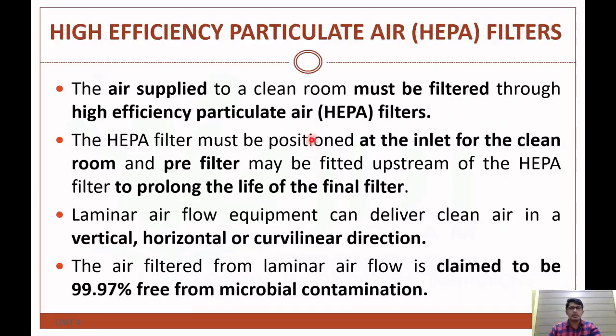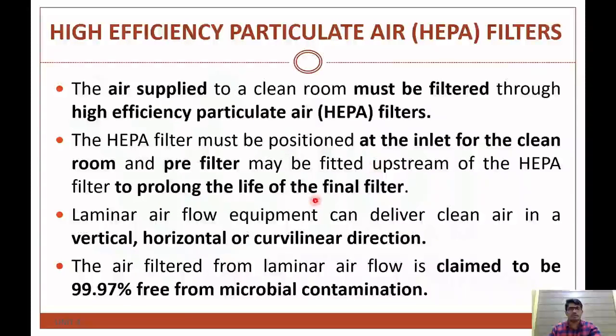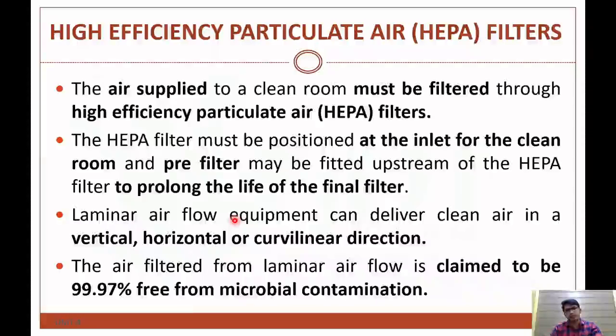The air supplied to the clean room must be filtered through a HEPA filter — that is, the High Efficiency Particulate Air filter. This filter must be positioned at the inlet for the clean room, and a pre-filter may be fitted upstream of the HEPA filter to prolong the life of the final filter. The laminar air flow equipment can deliver clean air in a vertical, horizontal, or curvilinear direction. The air filtered from the laminar air flow unit is claimed to be 99.97% free from microbial contamination.